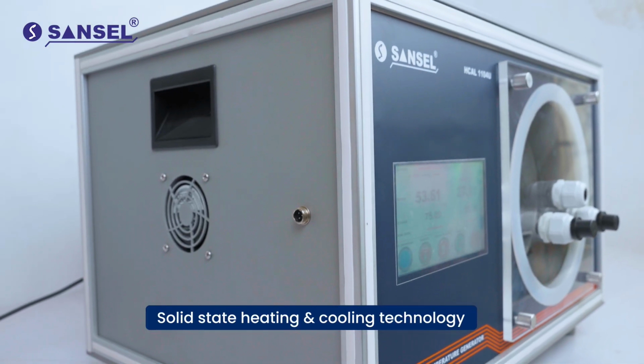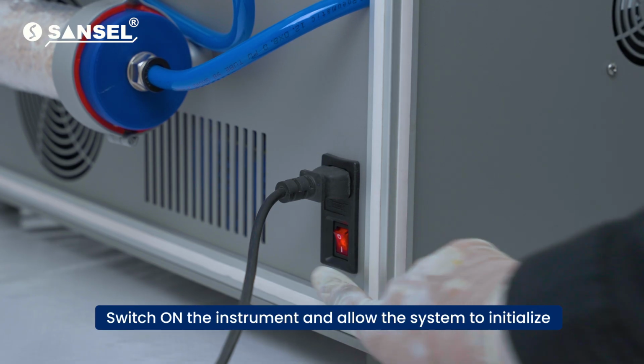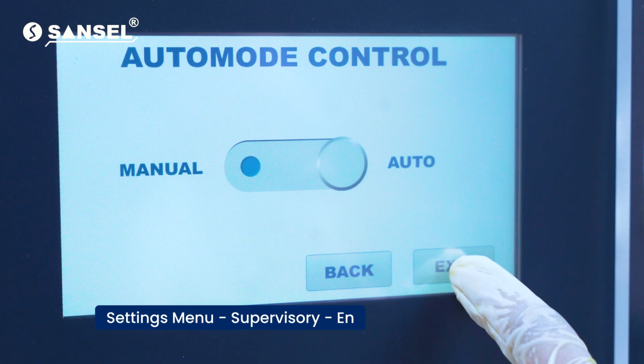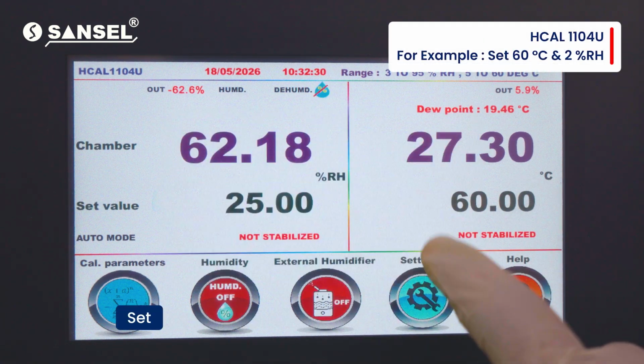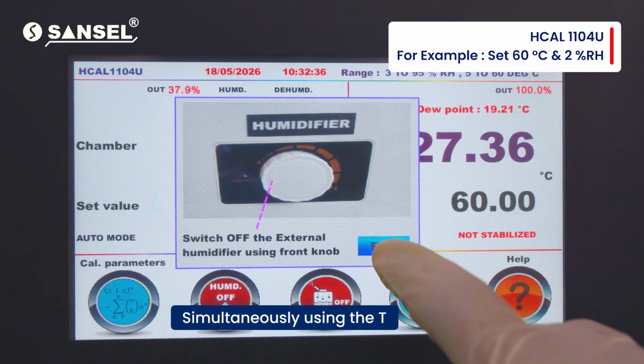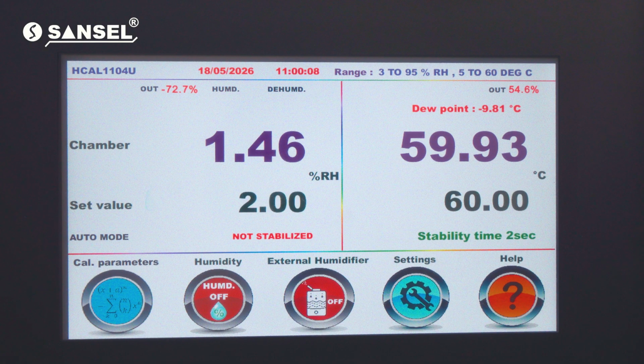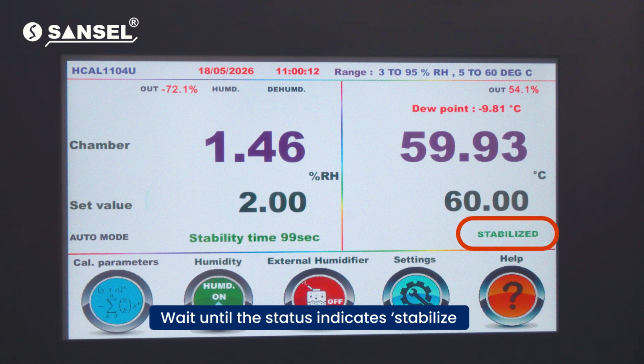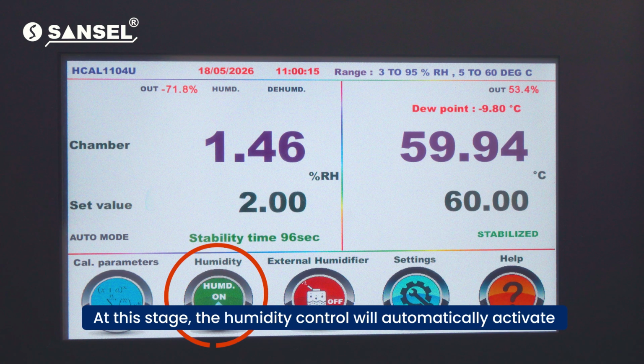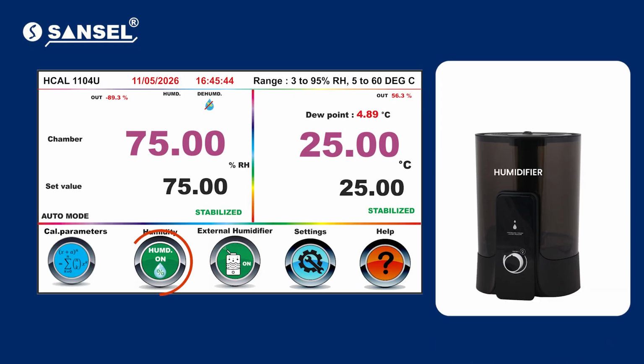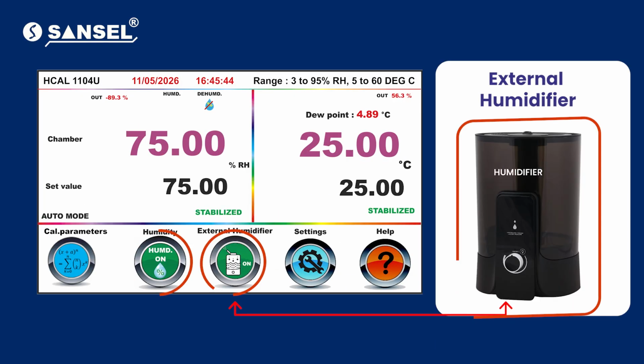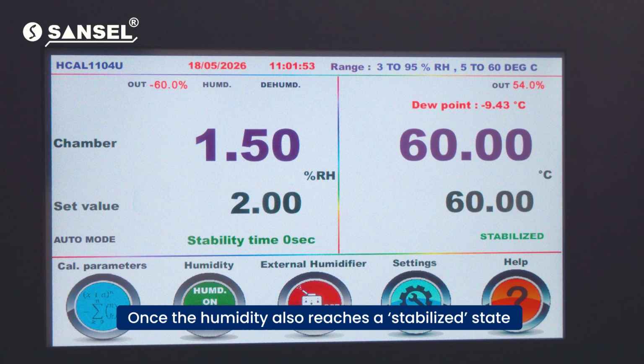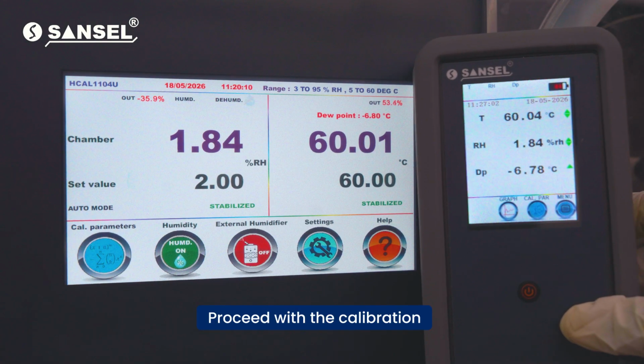The system is built with solid-state heating and cooling technology. Auto mode operation. Switch on the instrument and allow the system to initialize. Set the required temperature and humidity values simultaneously using the TFT display. Allow the system to reach the set temperature and wait until the status indicates stabilized. At this stage, the humidity control will automatically activate. The humidity system and external humidifier will then adjust automatically, switching on or off based on the set conditions. Once the humidity also reaches a stabilized state, you may proceed with the calibration.